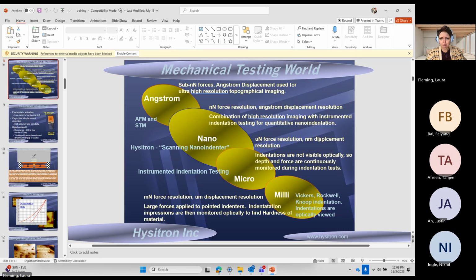We are continuously monitoring both the force and displacement during that test. That allows us to measure that hardness and modulus. On the other end of the spectrum is AFMs, where you're running a sharp probe across a sample surface, where you have sub-nanonewton forces, angstrom displacement, and you can get very high-resolution topographical imaging. Now, these are not indents. This is just a scan of the sample surface. There are some AFMs with tapping modes where you can interact with the sample and get some other information.